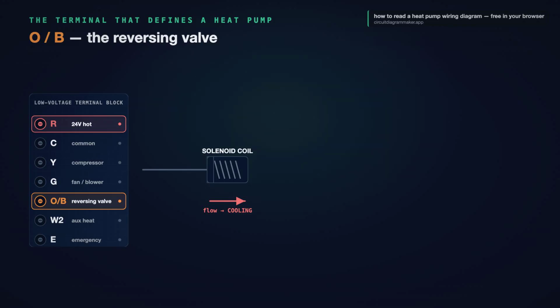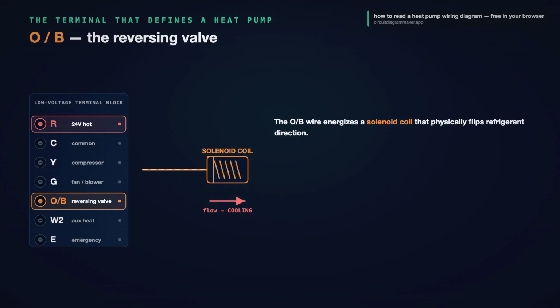Now the terminal that defines a heat pump, O or B, the reversing valve. Inside the outdoor unit sits a valve with an electric solenoid coil that physically flips the refrigerant's direction. The O or B wire is what energizes that coil. Here is the catch that trips everyone up. Brands disagree on when it is energized.